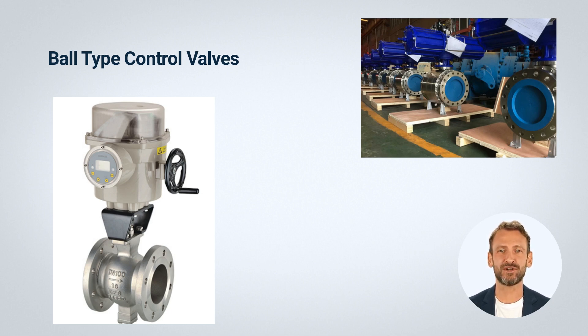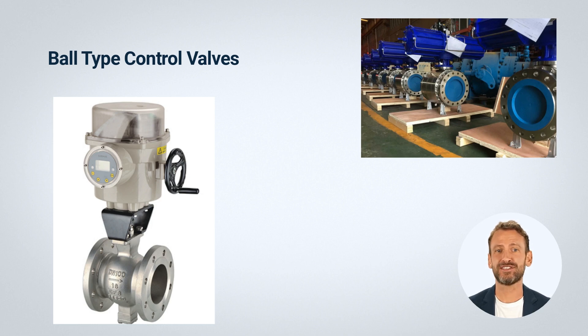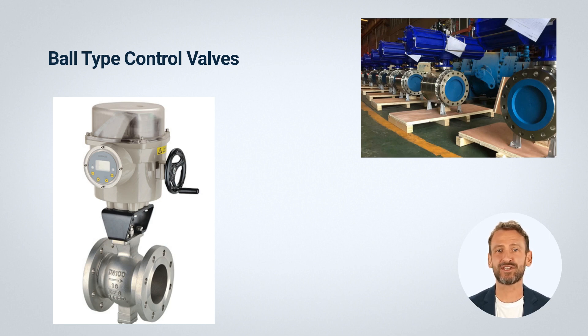Flow characteristics: ball valves offer good flow control and can provide bidirectional shutoff in some applications. They typically have a lower pressure drop than other valve types and can handle a wide range of fluids and temperatures. Function: ball valves are typically used for on-off service, but can be used for throttling if they have a specially shaped ball. They are well suited for applications requiring tight shutoff and high-pressure capabilities.